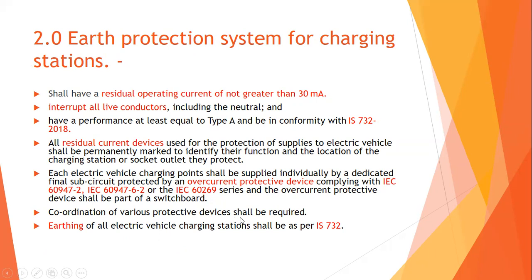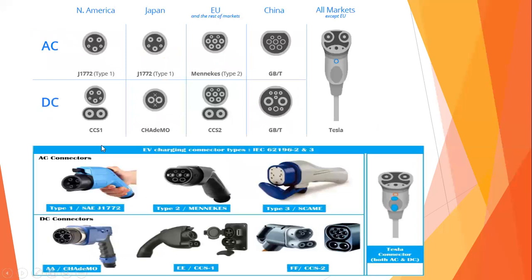The coordination of various protection devices shall be required — from the incoming supply right through to the electric vehicle, all protection devices should be coordinated. The wiring of all electric vehicle charging stations shall be as per IS 732. Various EV socket standards exist globally: in America the J1772 model is used for AC and CCS1 for DC; IEC 62196 is the IEC standard used internationally for EV charging connectors.